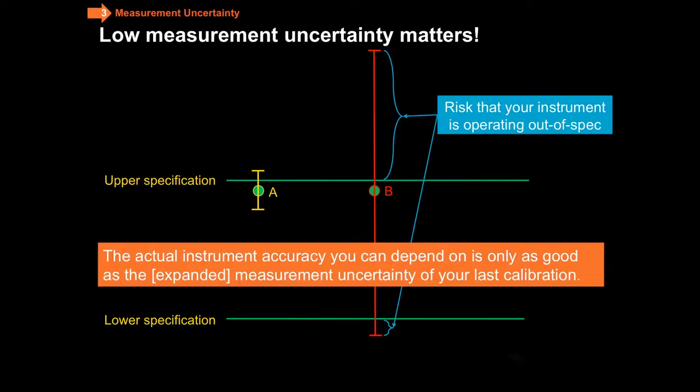The actual instrument accuracy that you can depend on is not just looking at the data sheet. What you can depend on is only as good as the measurement uncertainty from your last calibration. So I hope you can see that this is not just some esoteric concept. This is really important.